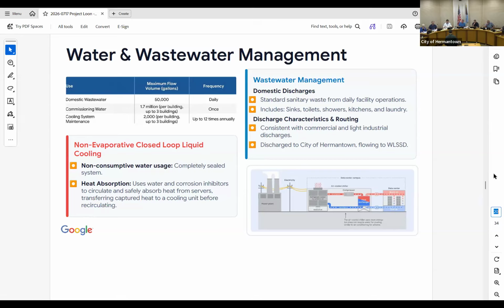Additionally, from the commissioning side, upon completion of each data center building there would be commissioning activities to charge the closed loop cooling system, flush it, and bring that system online at the end of each building. That would be up to 1.7 million gallons of flow, happening once or over a couple of days at the completion of each data center.